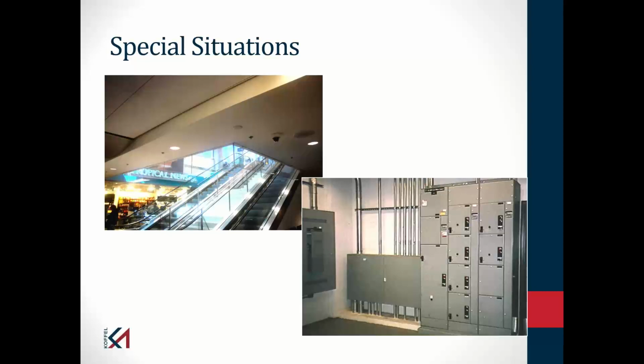Do you have fuel-fired equipment, or not fuel-fired? Do you have liquid transformers in there? Do you store combustibles in the space? What's the separation between the electrical equipment room and other spaces? That will all dictate whether I need to put a sprinkler in that space. If you are concerned about that sprinkler discharging on the electrical equipment, then I want to look at a different type of sprinkler system, like a pre-action system, in which somebody hitting the sprinkler, we will not get accidental water discharge out of a pre-action system, because I also have to have detectors in that space that would detect the fire before we discharge water.